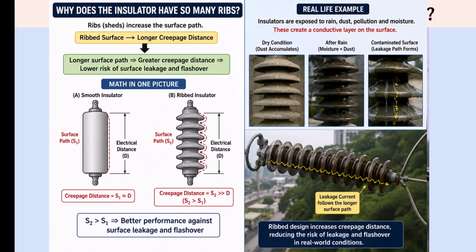Now, those strange looking ribs on the insulator suddenly make sense, right? They are not just changing its appearance, they are increasing the distance that leakage current would have to travel along the surface. So, those strange ribs aren't there because somebody thought they looked nice. Their geometry exists because electrical equipment must operate in the real world, and the real world contains rain, dust, pollution and moisture. This is an important lesson. Electrical engineers do not operate inside a perfect circuit diagram, our equipment has to survive outside.